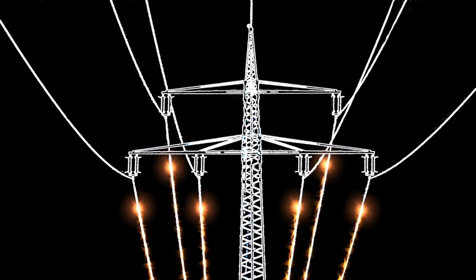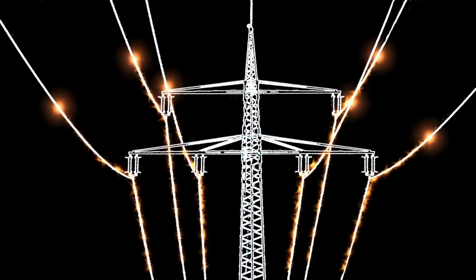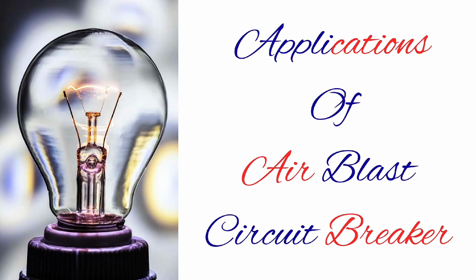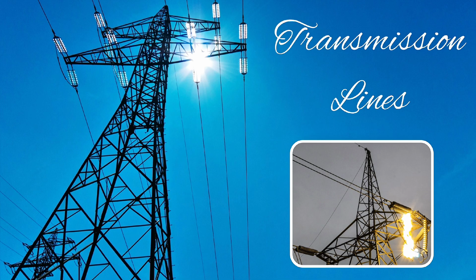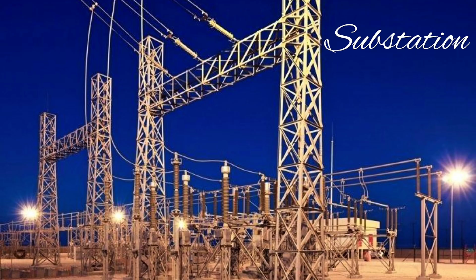Let us continue. Now that we have covered the types of air blast circuit breakers, where can we find their applications? Air blast circuit breakers, ABCBs, have a wide range of applications in power systems due to their reliability, speed, and efficiency. These applications include the following. 1. High-voltage transmission lines. ABCBs are used to protect high-voltage transmission lines from faults, such as short circuits and overloads. By quickly interrupting the circuit in the event of a fault, ABCBs help prevent damage to the transmission lines and ensure reliable power transmission. This is particularly important in high-voltage transmission systems, where faults can have significant consequences for the entire power grid.